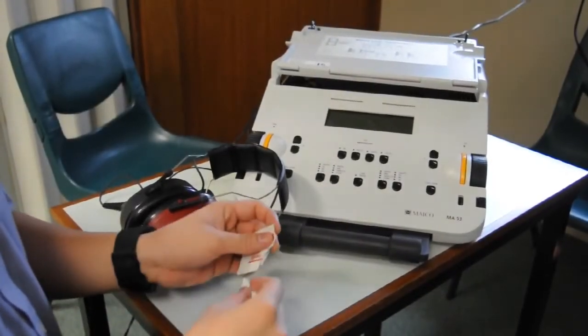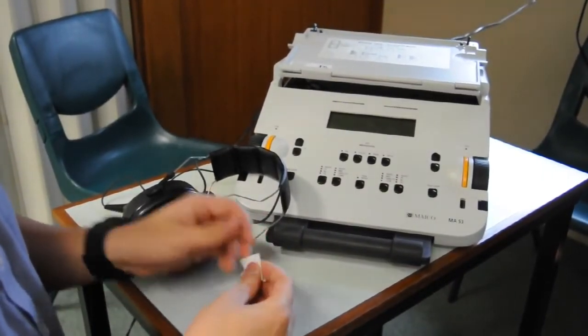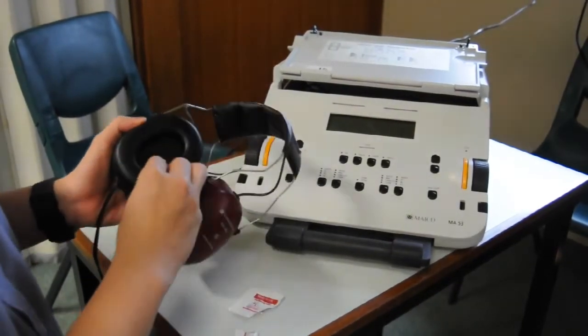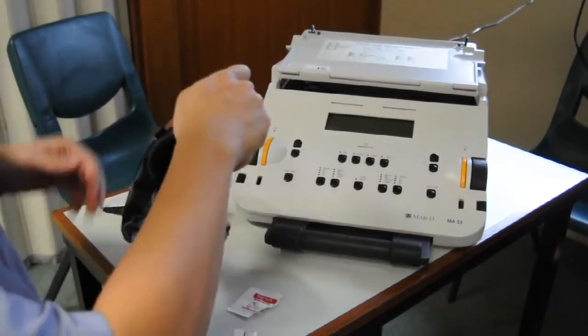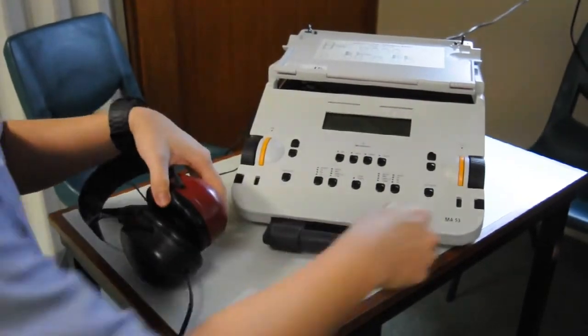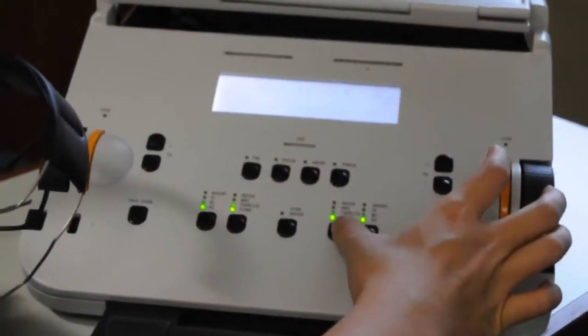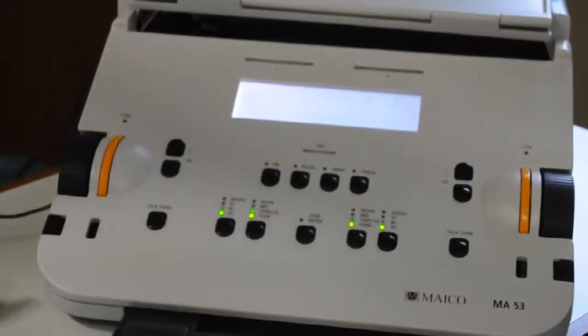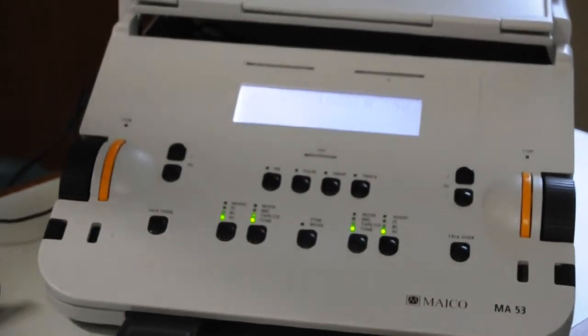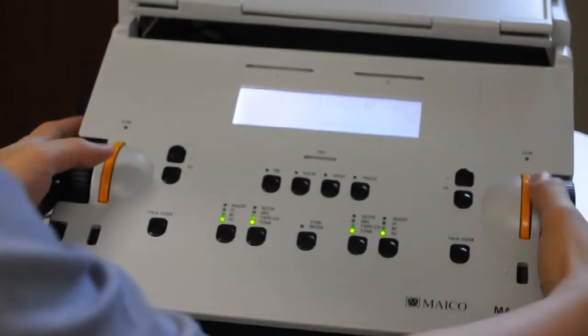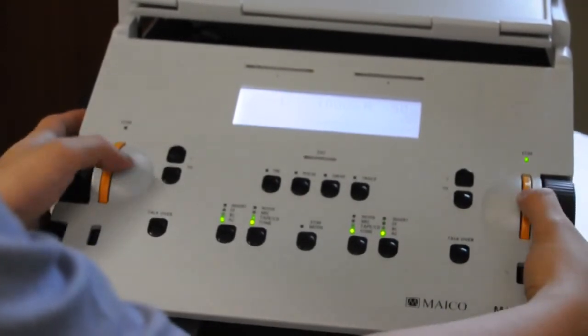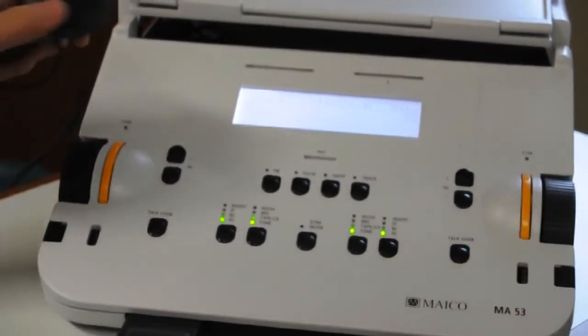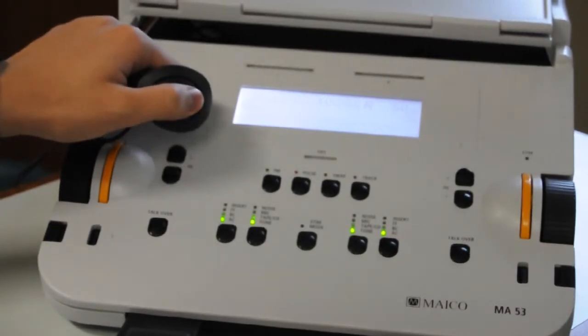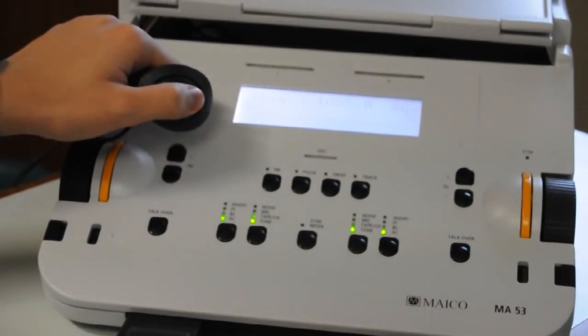Clinicians must wash their hands prior to seeing each client. Equipment that comes into contact with a client must be cleaned with an alcohol wipe, whereas insert headphone tips should be thrown away after a single use. Check the equipment at the start of every day. Put the headphones on, present tones across the frequency range to both ears individually, and check that the response button is working. Check the calibration sticker to ensure that your equipment is within its calibration period, and use alternate equipment if the equipment is either faulty or is out of calibration.